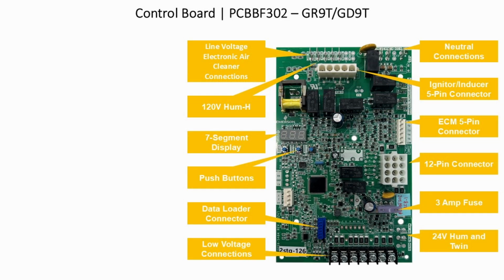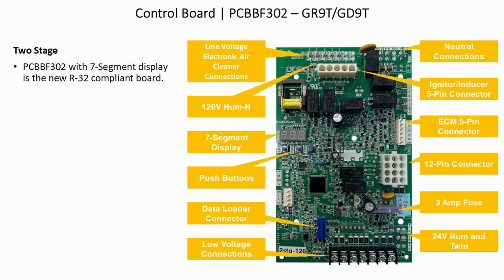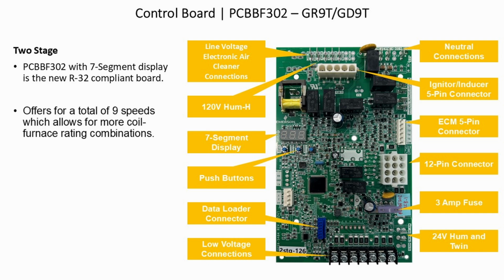Control board PCBBF302 for the GR9T GD9T furnaces. Two-stage PCBBF302 with the 7-segment display is the new R32 compliant board. It offers a total of 9 speeds, which allows more coil-to-furnace rating combinations.